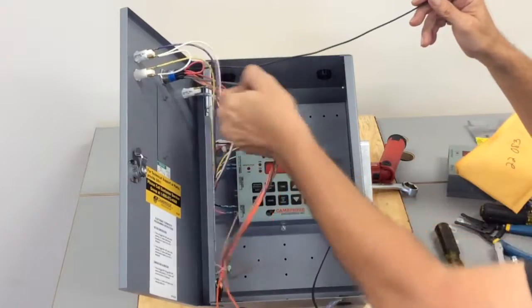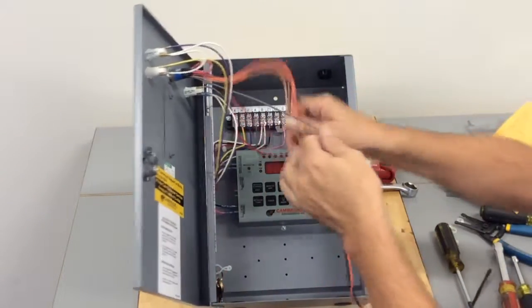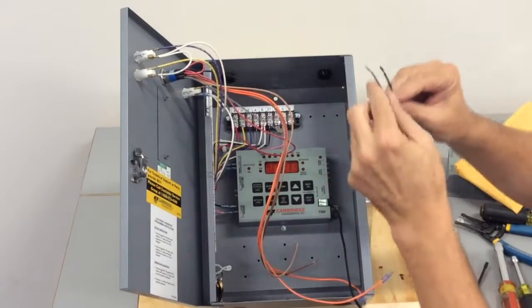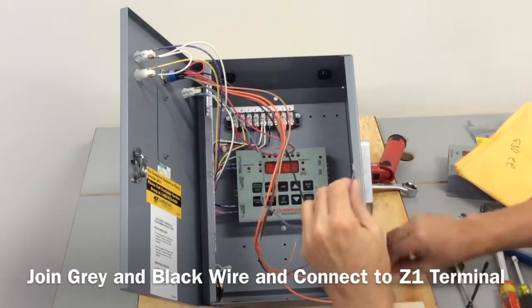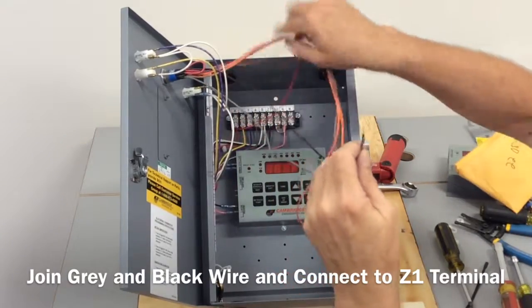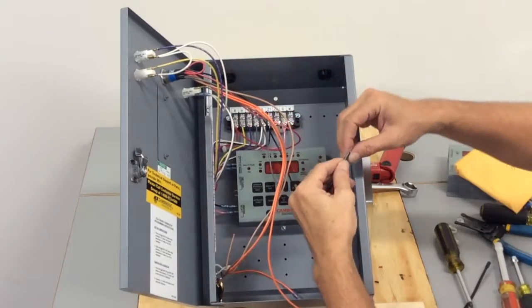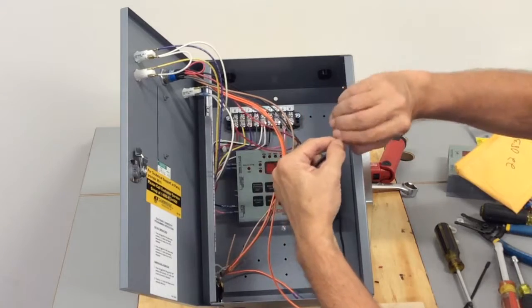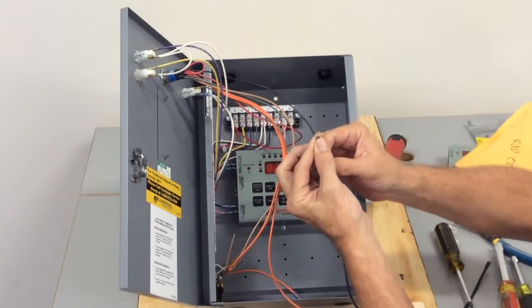The next wire, number three, and our gray wire, number four, they will be joined together so that we can place those on our Z1. I recommend twisting them together, maybe even stripping them a little extra, just so you get a better bite under that terminal.